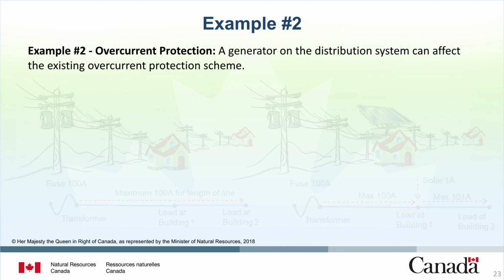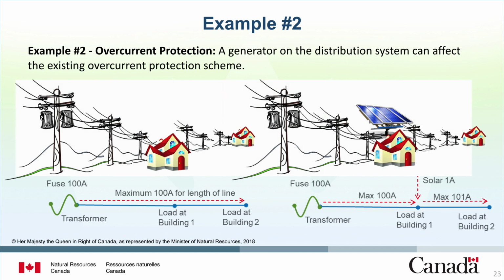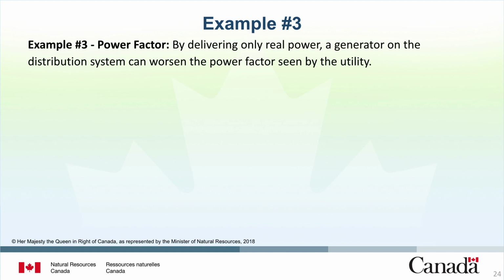As a second example, assume that a fuse limits the current coming from a transformer to a value that is less than what the line is rated for, 100 amps in this example. Interconnecting a generator somewhere down the line might add current in excess of what the line can carry and void the overcurrent protection scheme. In this example, even one additional amp would require the utility to change the overcurrent protection scheme. The third and final example is regarding the power factor.